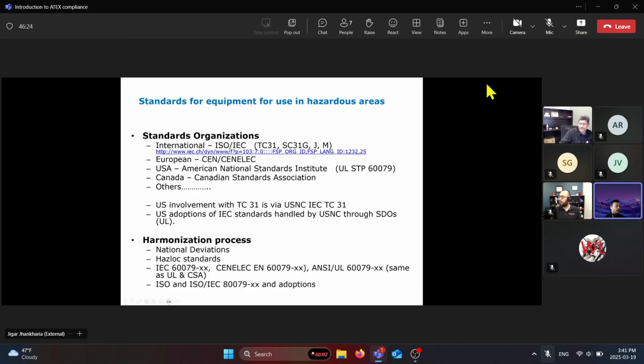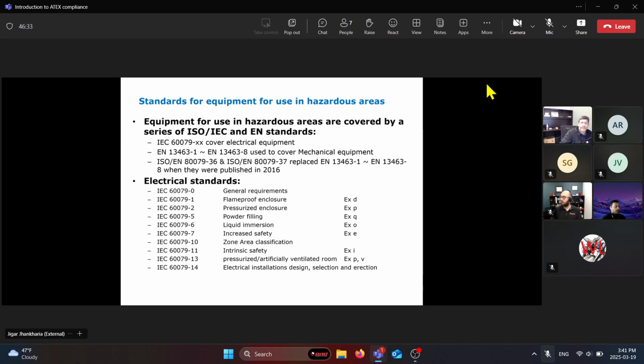Okay, there we go. So that's the basis of adoption of standards, harmonization of different standards from IECEx, ATEX to North America. Now we get into the different methods of protection that we've been talking about. Basically, there are standards for electrical equipment and standards for non-electrical equipment for certification for both IECEx and ATEX. So -0, the 60079 series, is for all standards related to hazardous locations. -0 is the general requirement. Anytime you get a product certified for ATEX or IECEx, that's going to be the base standard.